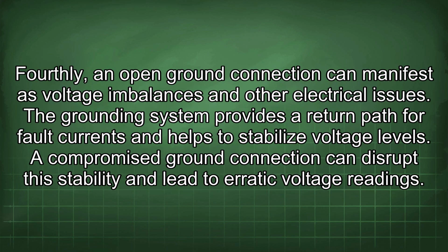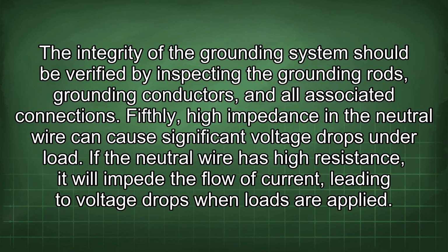Fourthly, an open ground connection can manifest as voltage imbalances and other electrical issues. The grounding system provides a return path for fault currents and helps to stabilize voltage levels. A compromised ground connection can disrupt this stability and lead to erratic voltage readings. The integrity of the grounding system should be verified by inspecting the grounding rods, grounding conductors, and all associated connections.